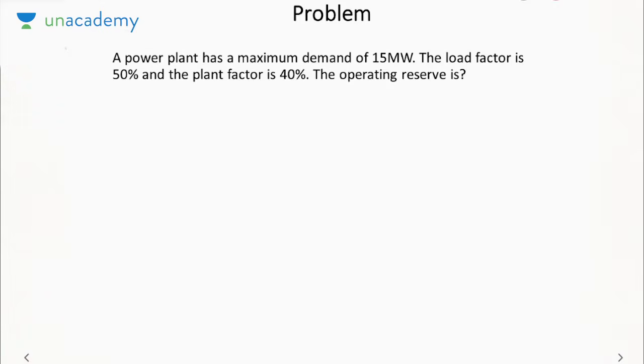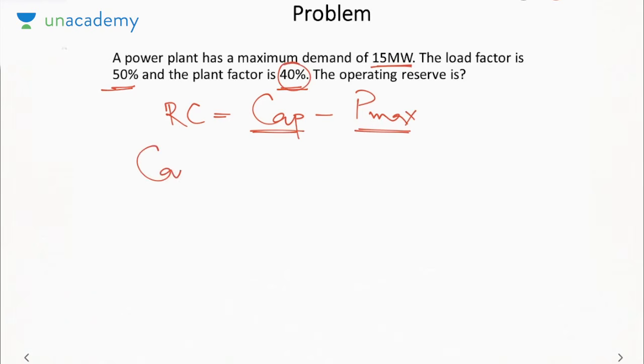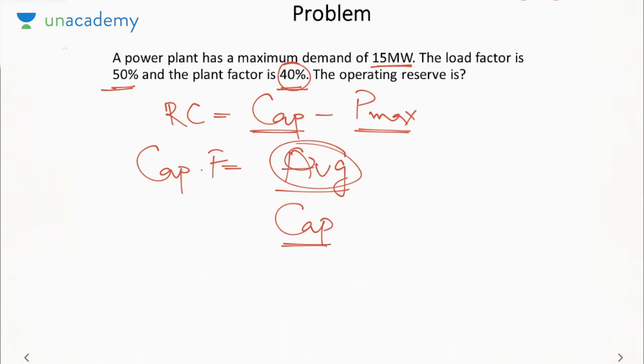In our next problem, it is saying a power plant has a maximum demand of 15 megawatt. The load factor is 50% and the plant factor, that is the plant capacity factor, is 40%. We need to find the reserve capacity. So reserve capacity is capacity minus maximum demand. Okay. So we know the maximum demand. We need to find capacity. We know the capacity factor. Capacity factor is average demand by plant capacity. For that we need average demand.